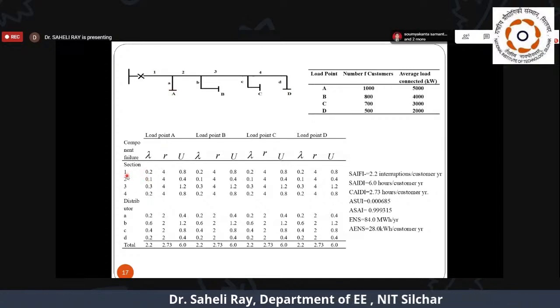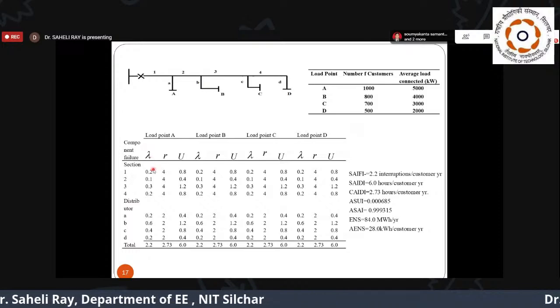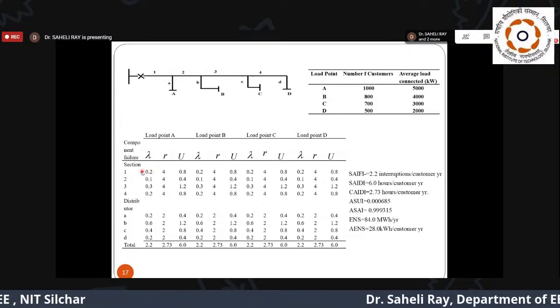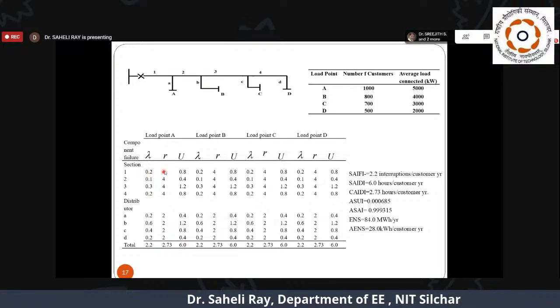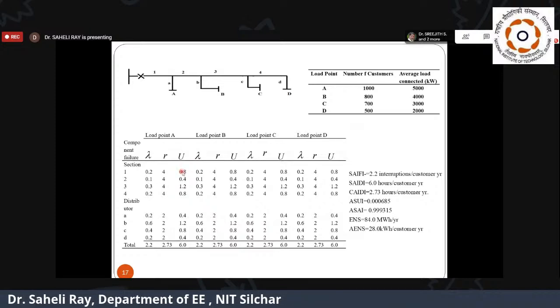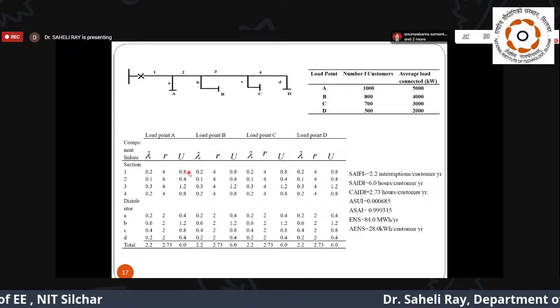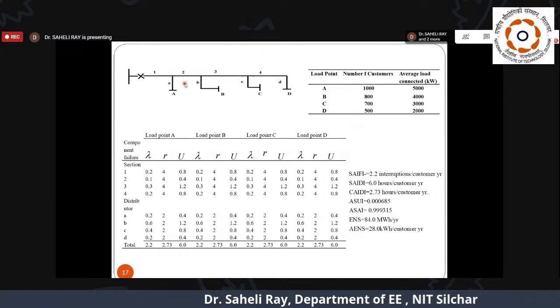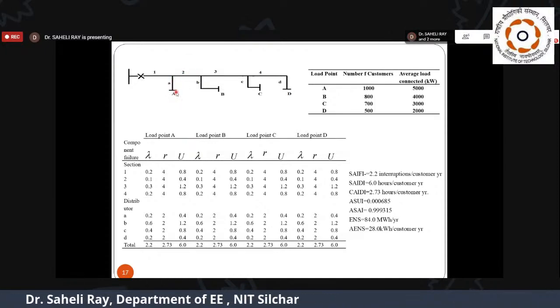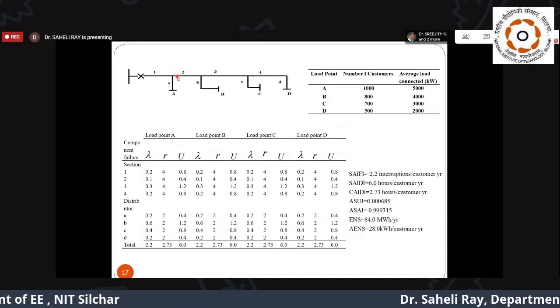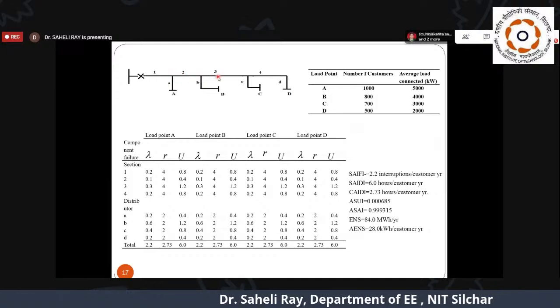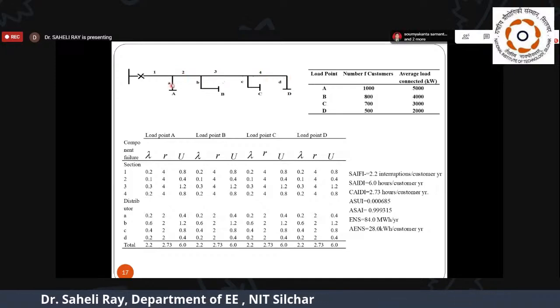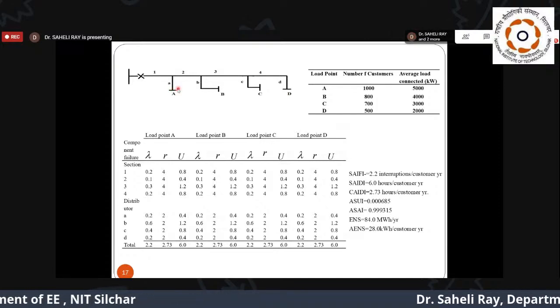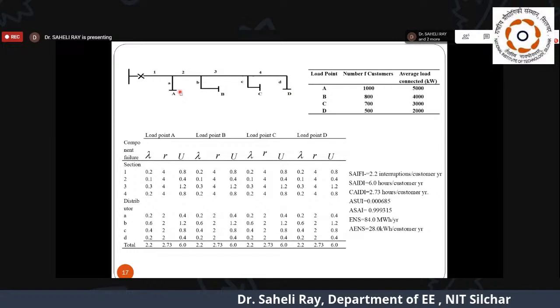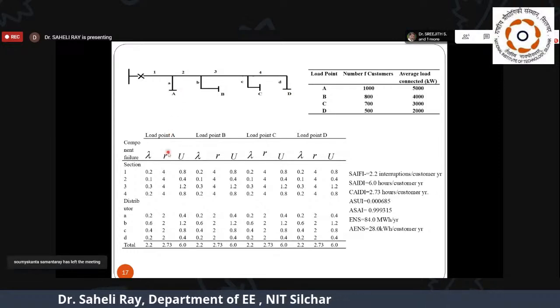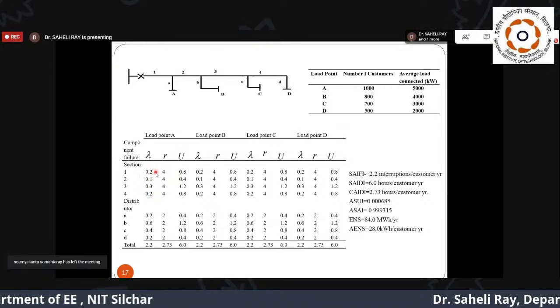Right? So corresponding to section 1, load point A is affected. Section 1's failure rate comes into the picture, 0.2, and the repair time is also 4. Multiplying 4 by 0.2 gives 0.8. Now if a fault occurs in 2, the same thing happens. Power is disconnected, and no other protection device is there for isolating: no fuses, no circuit breakers, nothing. So wherever the fault is, everything is connected together, and this load point will be affected. It will come under the faulty portion, and until the fault is repaired, power will not be resumed to that point. As a result, all these faults affect the load points.